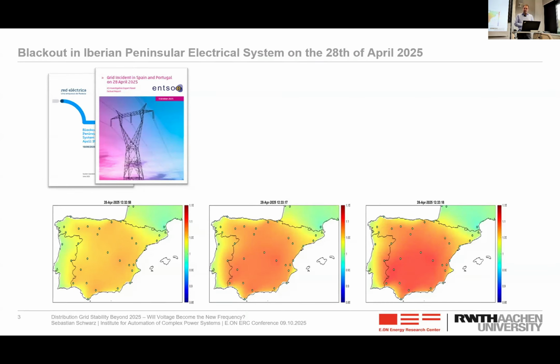That of course mitigated and stopped the oscillation, but it came with side effects. The first one was that because you have a reduced impedance, your voltage in the system automatically increases. And because you are exporting less active power, that also means your local generators have to generate less active power. Now, the issue is that most of the generators on the local level, basically PV and wind, operate typically on a fixed P and Q type of control, so if you decrease the active power, you also automatically reduce the capability to provide or absorb reactive power. In this case, because we were generating, they were all in an absorbing state. So that again led to a rise of voltage.